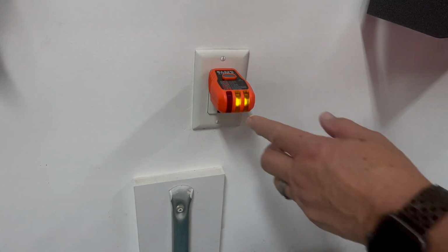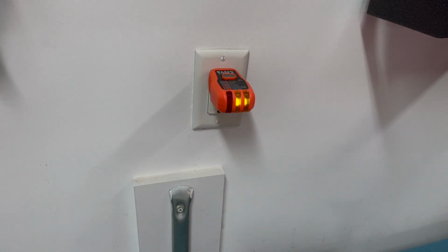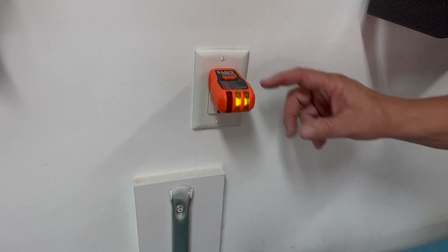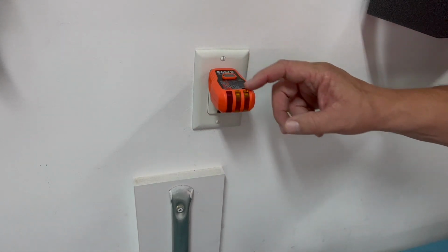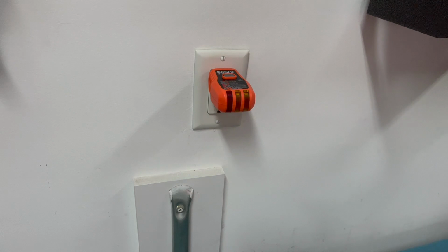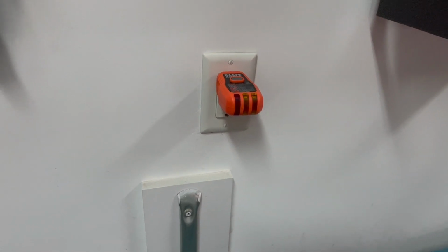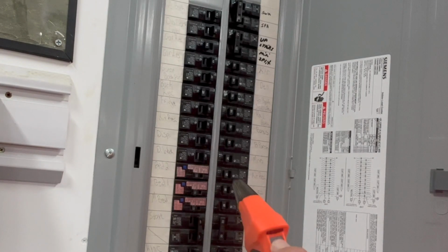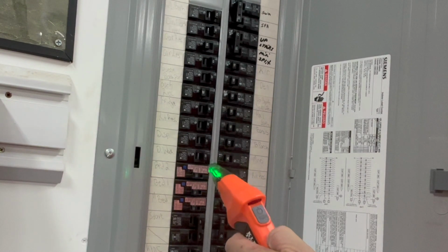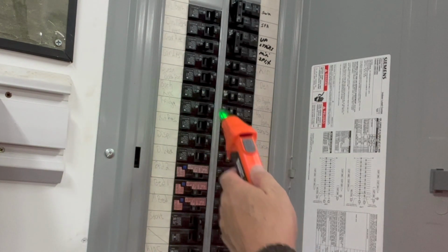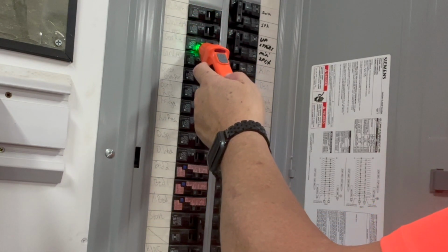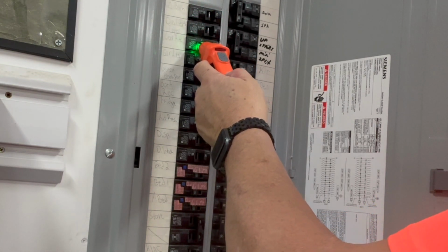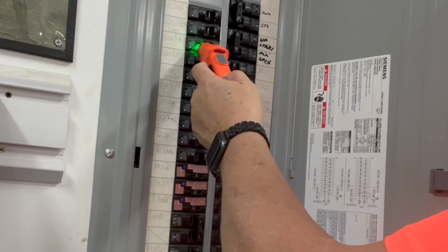You can see the two yellow lights indicate that the wiring is correct. Now, let's test the ground fault plug, the GFCI. You do that by pressing this button on the top, and it indicates that the circuit is off. So now let's go back to the circuit breaker and verify that it is indeed off. Okay, to verify that it is indeed off, you want to scan it again. You just turn the receiver back on again, and circuit number 3 is the one that's again indicated no power.